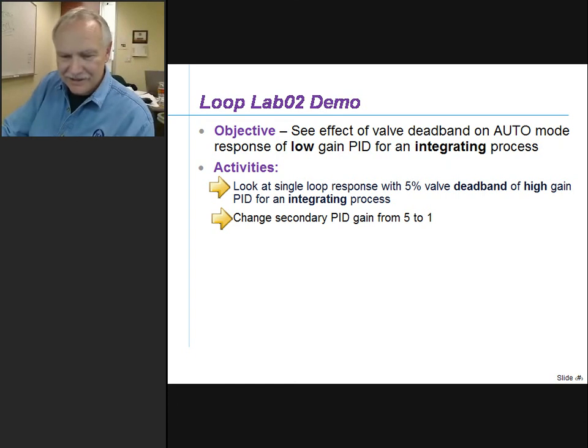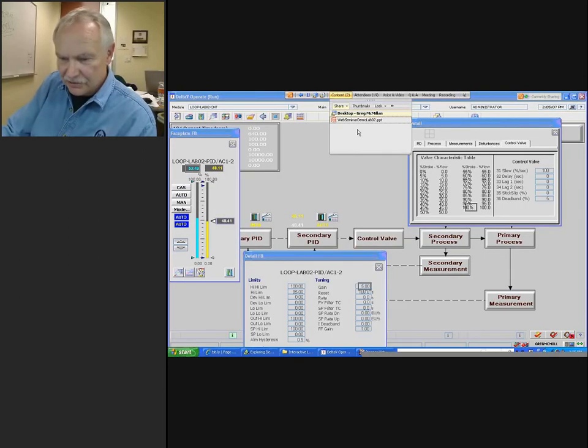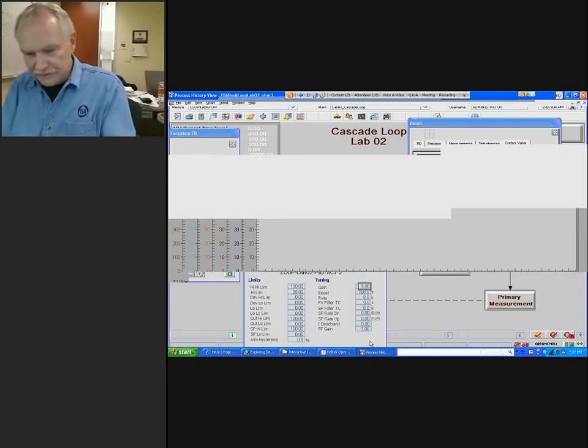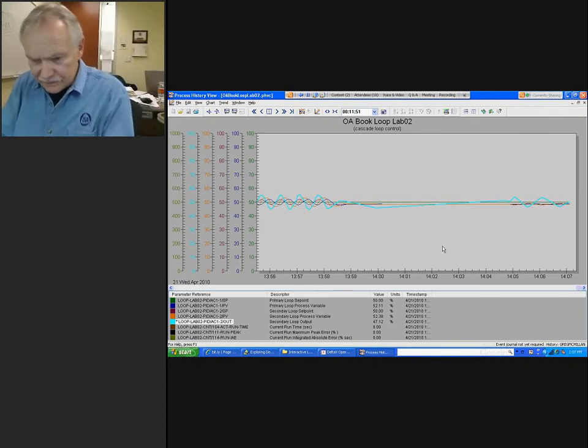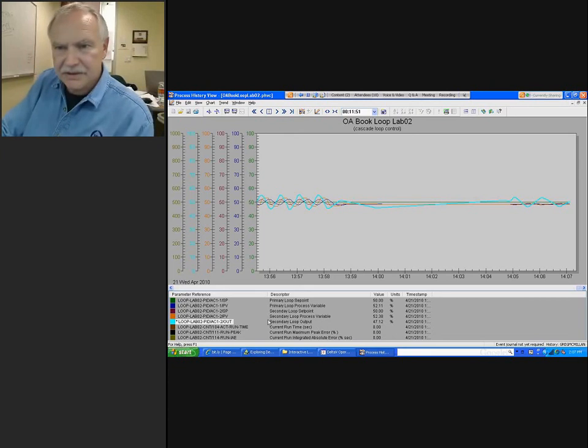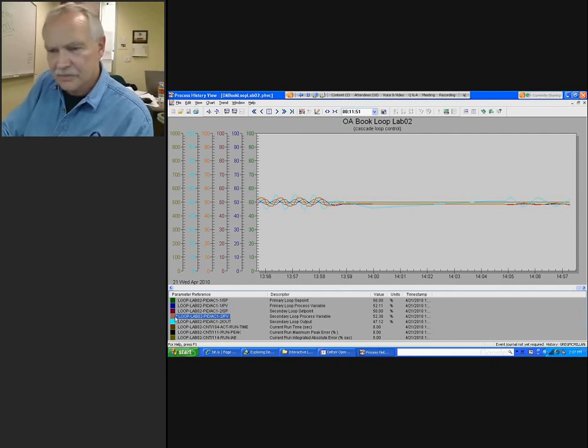We can see the sawtooth most evidently in the controller output. And we have to look pretty close to see it in the process variables, but it is there. Principally, the reason it's so small in the process variables is because we have the higher controller gain. Let's see the effect of lowering that controller gain from 5 to 1. And while that response is developing, let's go back to the webinar slides and see if we can wind up what we're trying to talk about.